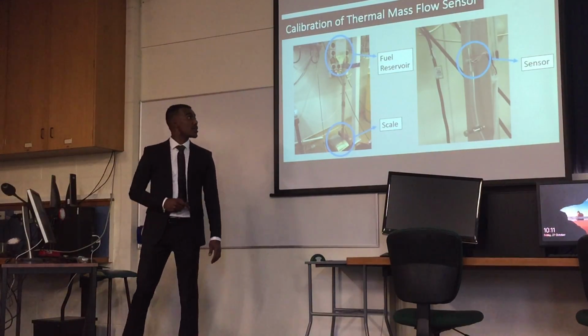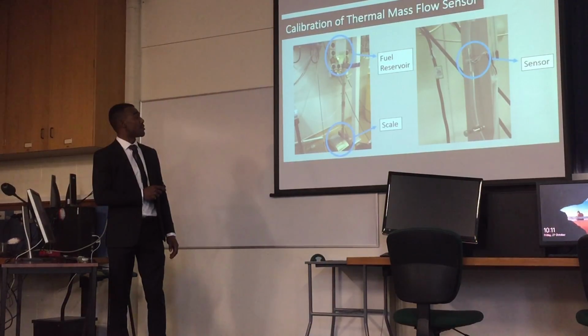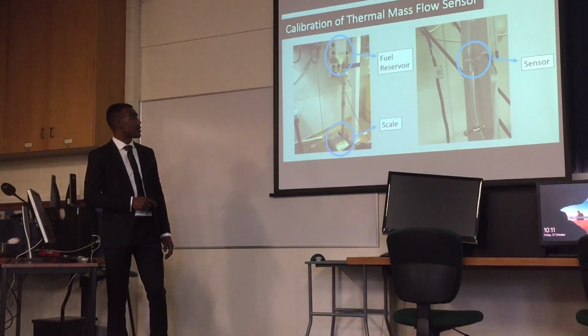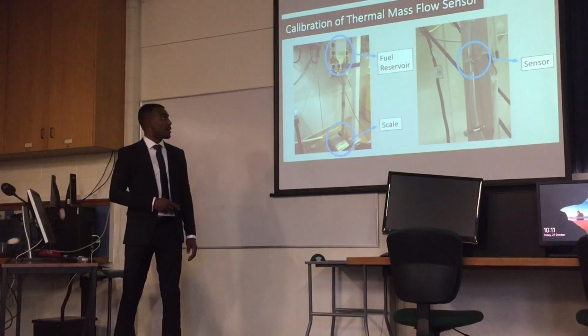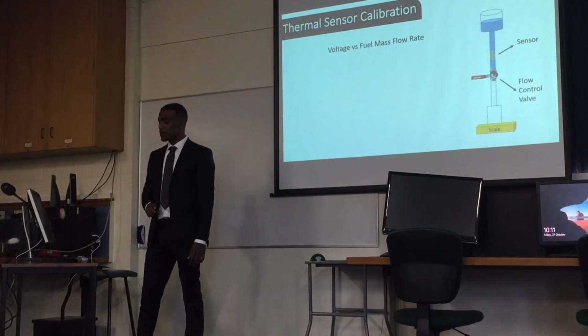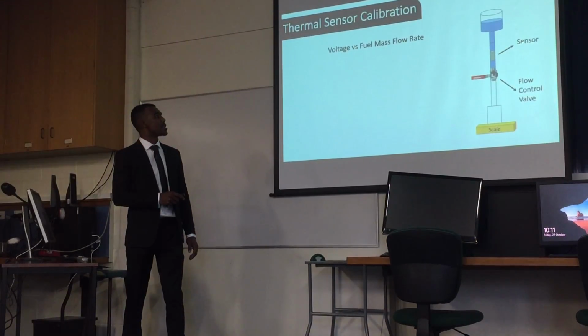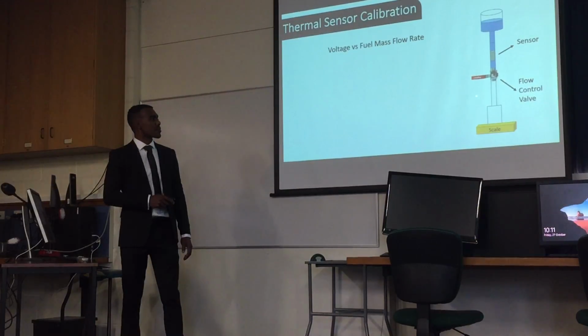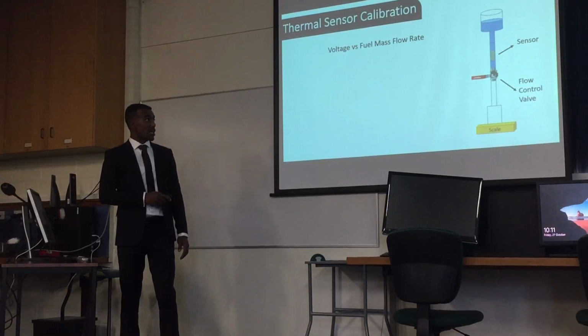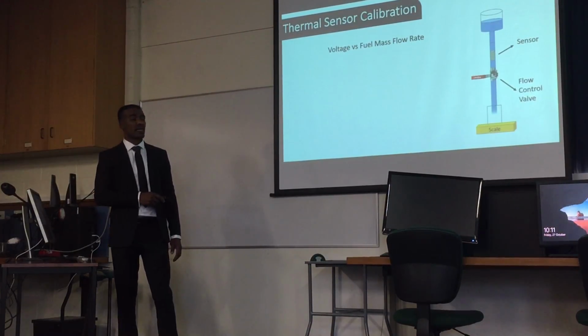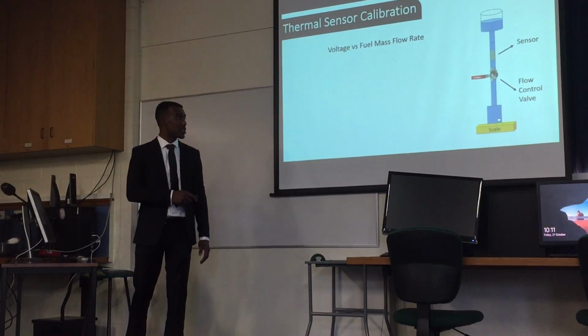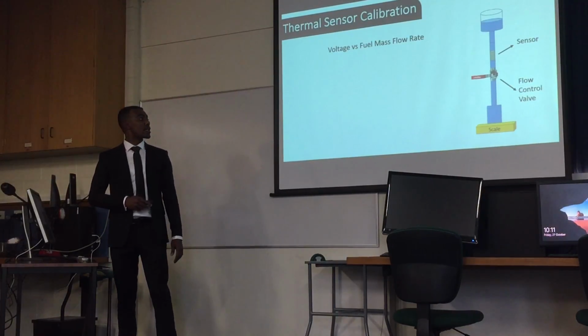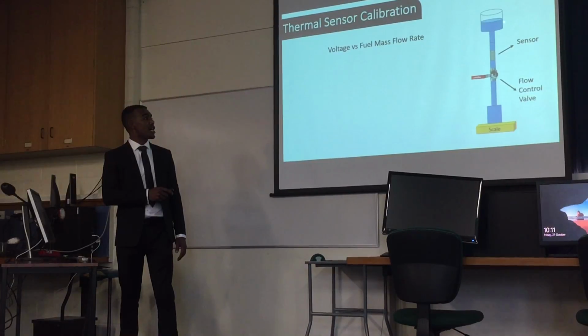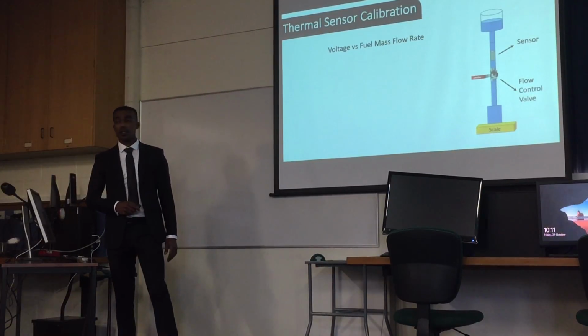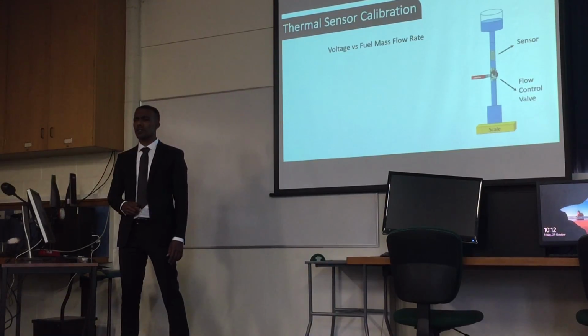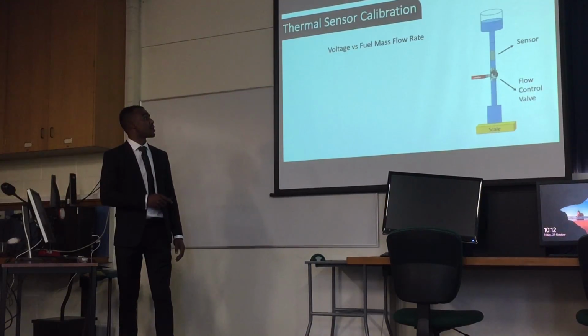We took it from there and put it inside a system to calibrate it, and you see the system here. You have the fuel reservoir at the top, and we have a scale, and the sensor is in the middle here. You see this is a zoom. To explain it further, look at the next one. We have the fuel on top, the sensor, and a flow control valve. To calibrate it, we open the valve and, at a certain flow, measure the mass accumulation in the jar and calibrate against that. We also considered the static pressure from the height change, and it's actually very small, about 0.01 millimeter over 1 minute, so it's negligible.